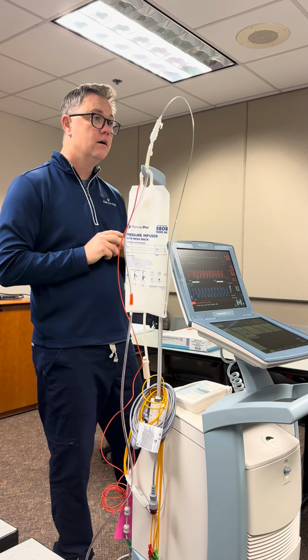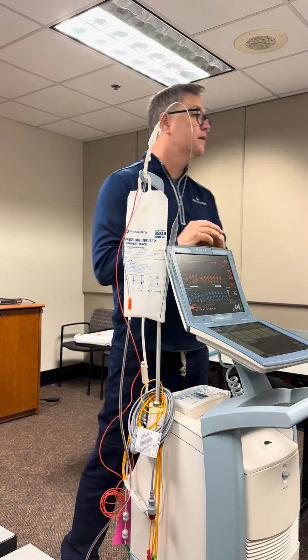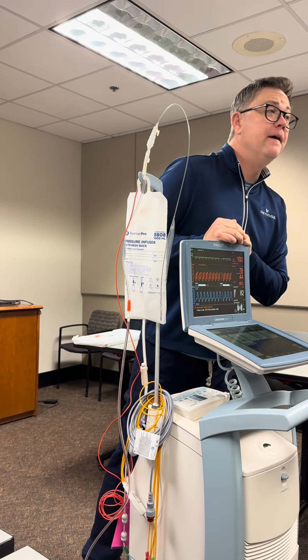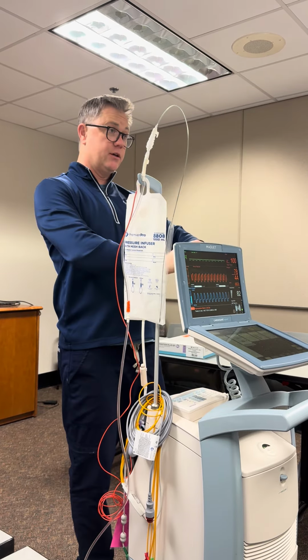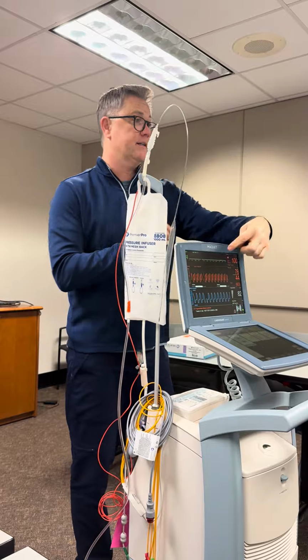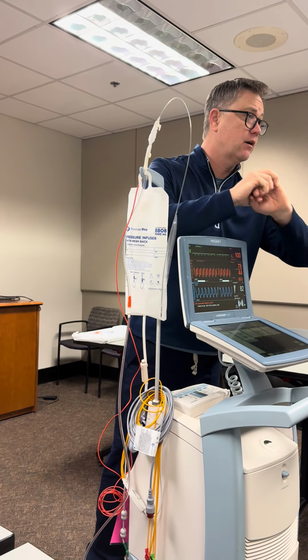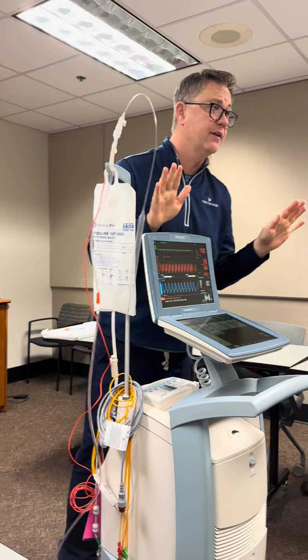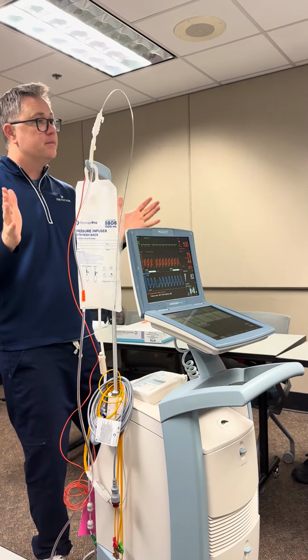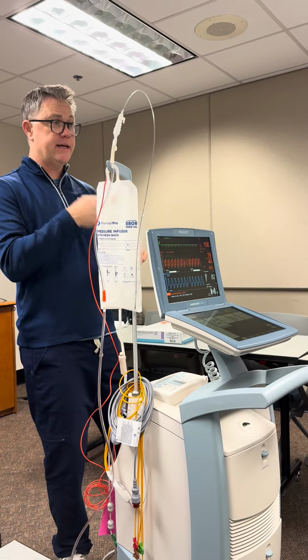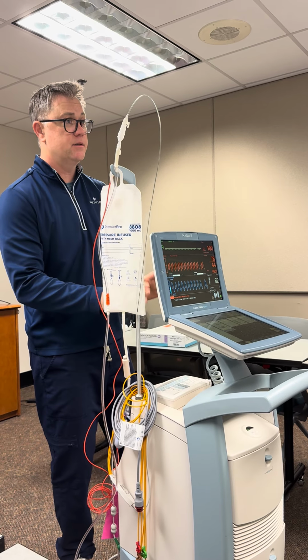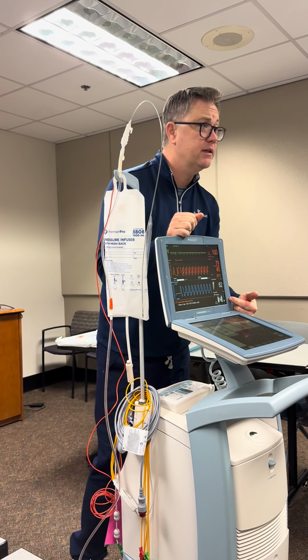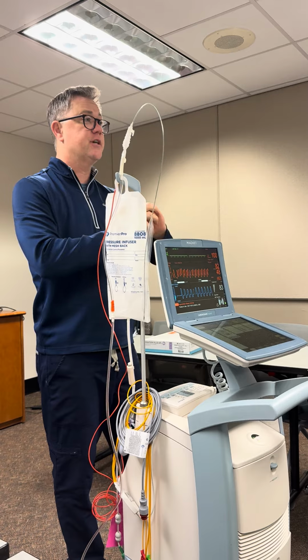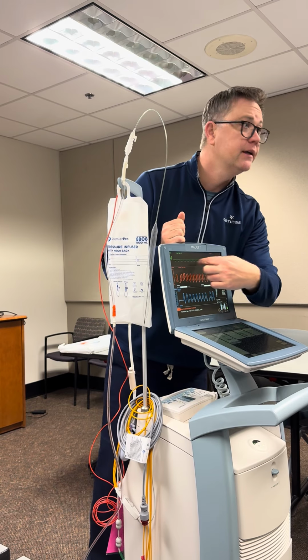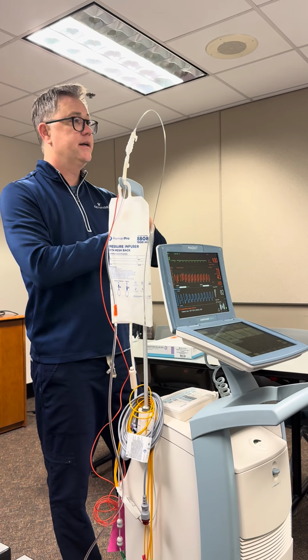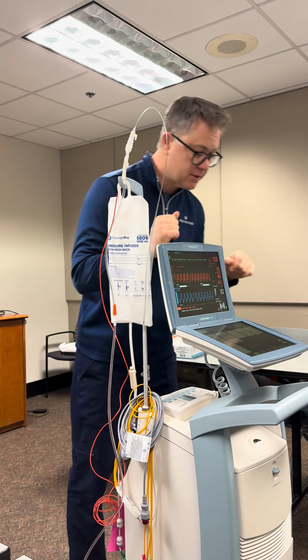Isn't there a CPR light though? Is there a CPR mode? No. Okay. So it'll just recognize those. You're doing your chest compressions, and it should recognize that as a pressure trigger and augment your chest compressions. So yeah, nothing you need to do to the pump. I mean, if you want to force the machine into it, you could take a lead off or pull the EKG cable. That's going to automatically put it into the pressure trigger, but it should recognize those chest compressions as a pressure trigger. You don't have an EKG signal anymore, so it's going to time off of those chest compressions.